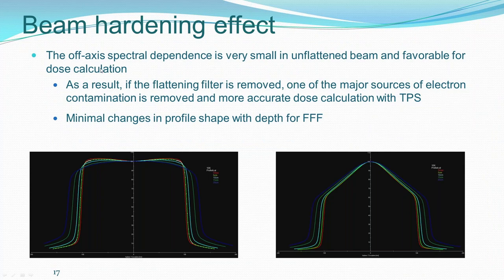The off-axis spectral dependence is very small in the unflattened beam — the spectrum is almost the same across the beam, which is favorable for dose calculation. Because there is no flattening filter, electron contamination is also removed, so the TPS can do more accurate calculations. Because of the spectral effect between central and off-axis in a flattened beam, the beam profile shape changes with depth. But for an unflattened Triple F beam, the shape remains the same at all depths — only the divergence causes the profile to be wider.